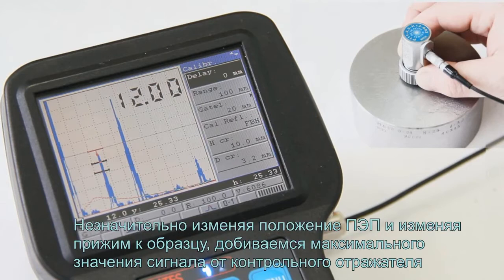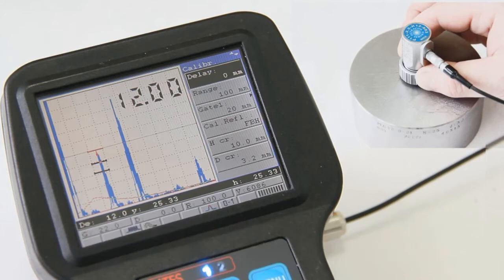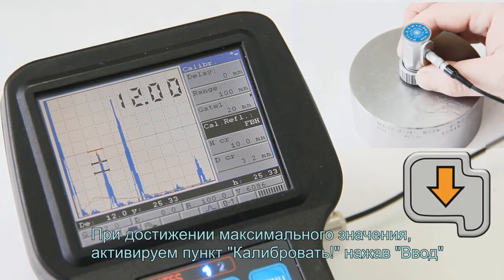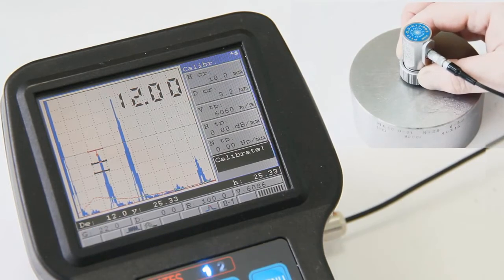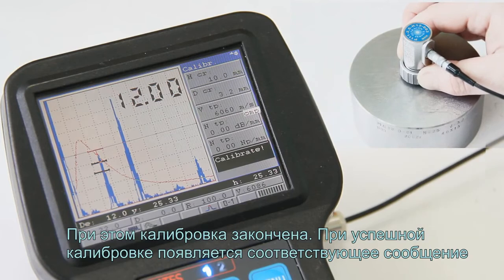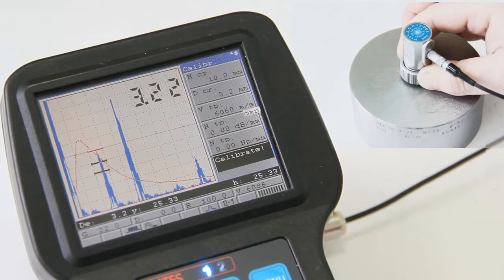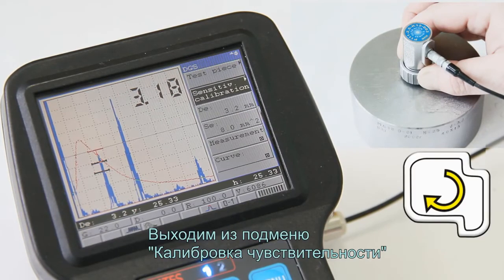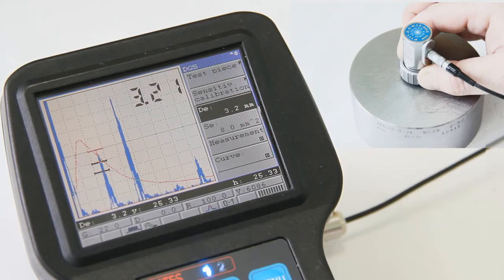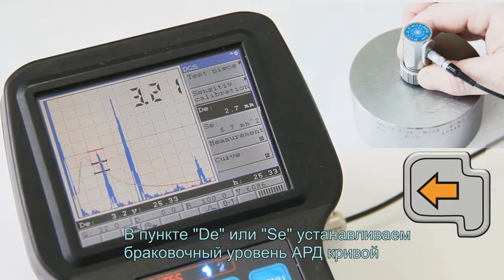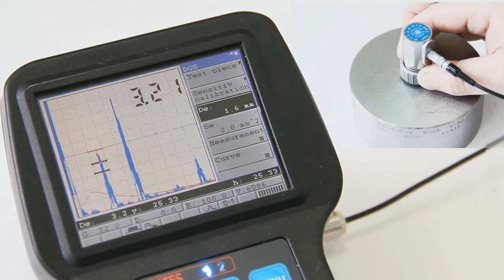Slightly change the probe position and change the probe pressure to the block to achieve the maximum value. When you achieve the maximum value, activate the Calibrate item by pressing the Enter key. The calibration is finished in case successful calibration following inscription is appeared. Exit the submenu Sensitivity calibration. In DE item, Acceptance equivalent diameter, or in SE, Acceptance equivalent area, set the acceptance level for DGS curve.